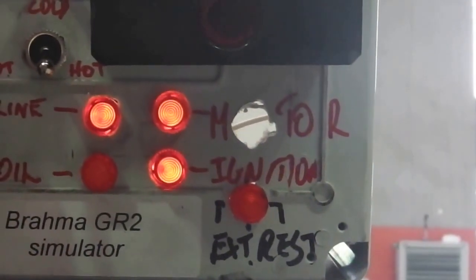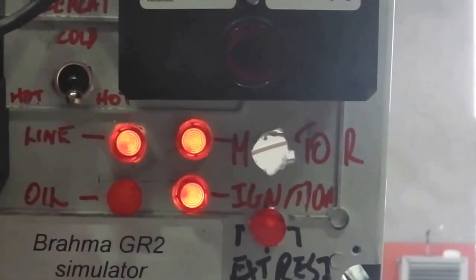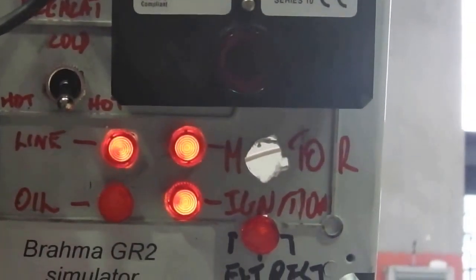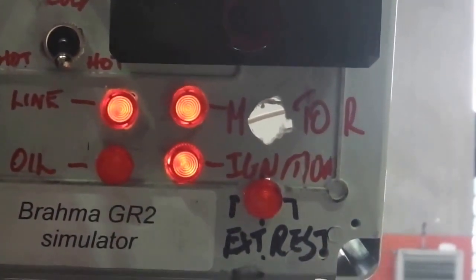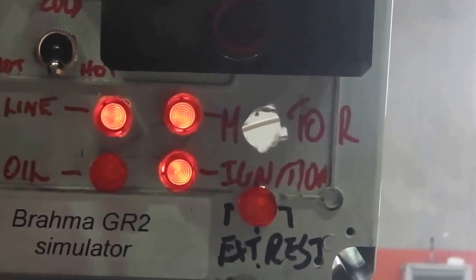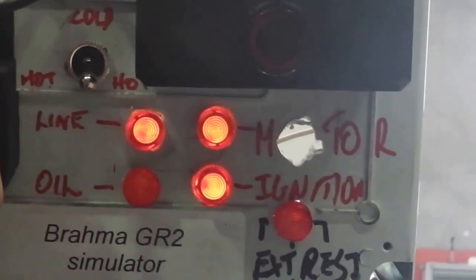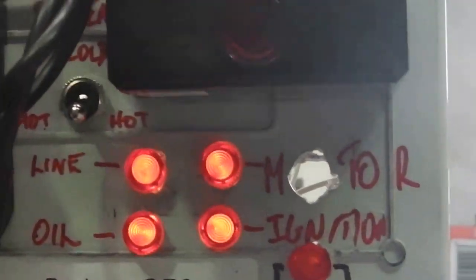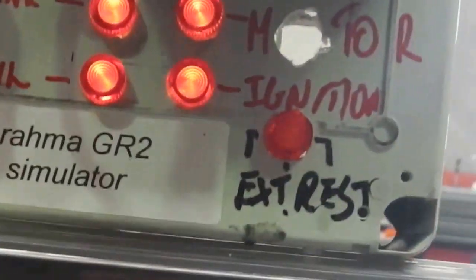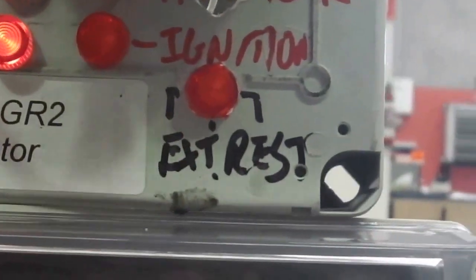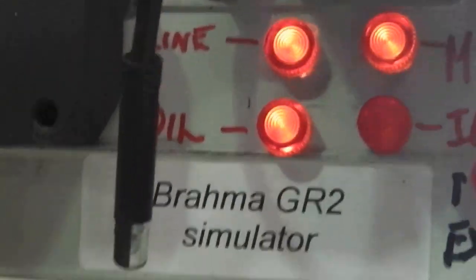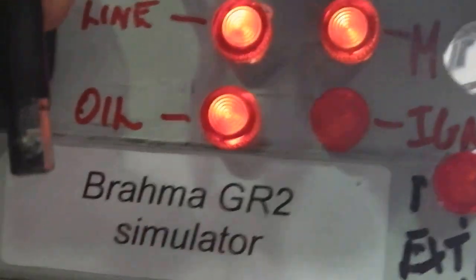Ignition's on, motor's on, line's on. There'll be a purge delay here of about 15 to 18 seconds, and then we'll see the oil come on soon. When that happens, I'll release the photoelectric cell. There you go. And the little old controller there thinks that everything's honky-dory because the photoelectric cell here is picking up light, so we've fooled the controller into thinking we've got a nice flame in our combustion chamber.